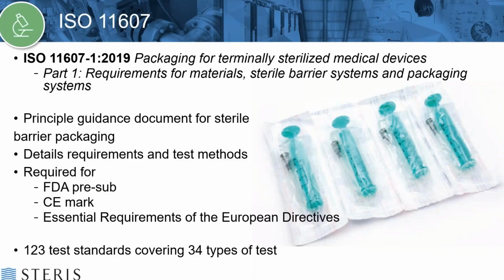So we'll talk now about sterile package testing. This is all based on ISO 11607. This is the principal guidance document for sterile barrier testing. So it's a packaging for terminally sterilized medical devices. This details all the requirements for validating the package for your device and all the test methods that can go along with that. This is required for regulatory submissions, so your FDA submissions, your CE mark, the essential requirements of European directives.